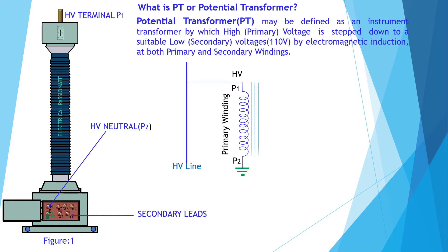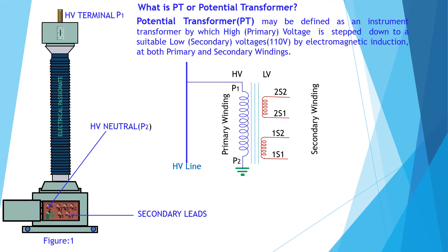These are the secondary windings. Two or more windings of small turns are used as secondary windings. 1S1 and 1S2, and 2S1 and 2S2 are the secondary terminal connections. The system voltage is applied across the terminals of the primary winding of the transformer, and then proportionate secondary voltages appear across the secondary windings.